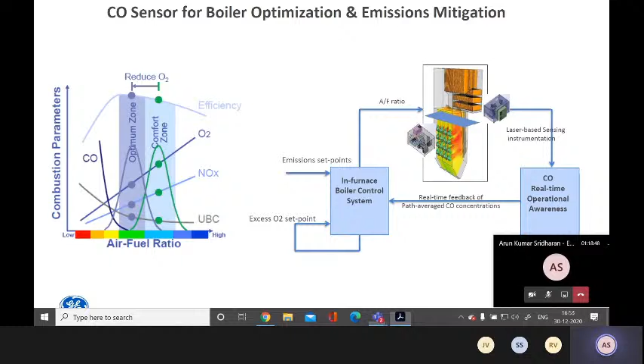And when you operate a coal power plant at low loads, the flame can die out. In order to make sure that the flame doesn't die out, you need a pilot flame. And that pilot flame is generated by burning oil. Now, ideally, you'd like to get rid of oil because it has high operational expenses if the coal plant is operated at part load for a long time. And oil also contains a lot of sulfur, which leads to a lot of corrosion issues. So we want to be able to get rid of oil burners.